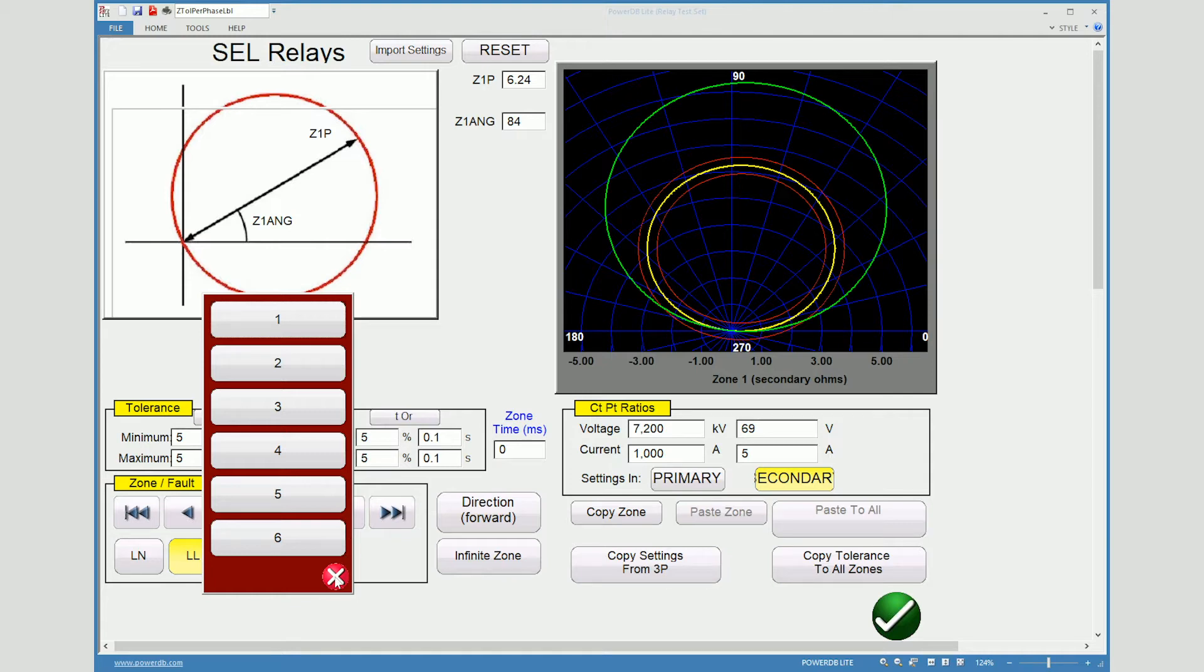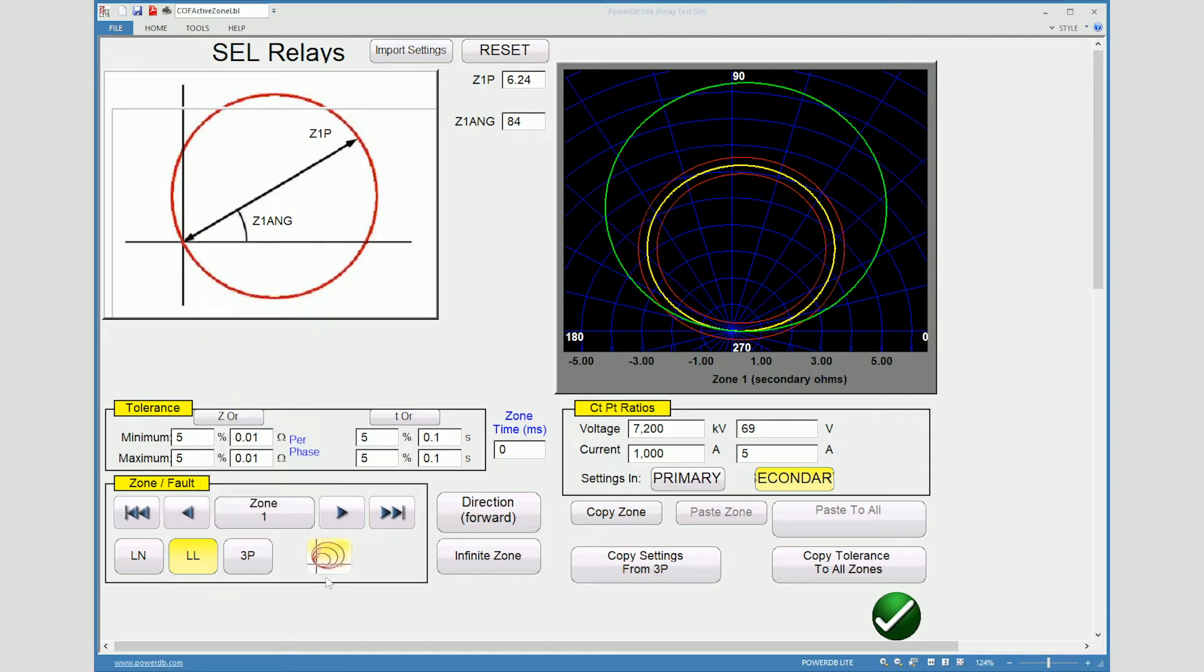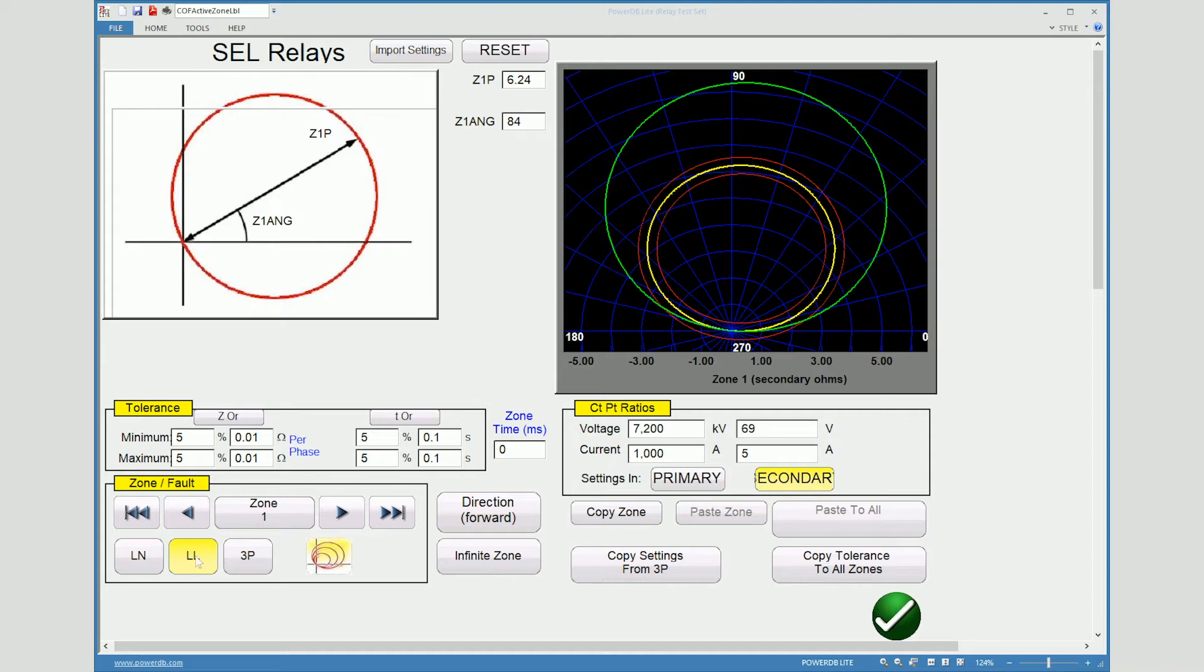So for zone one we will also pick which style of test we want to run. We can go line to ground, line to line, or three phase. Here you'll notice that we have the line to line function highlighted, which is our normal test that we do for zone impedance elements.